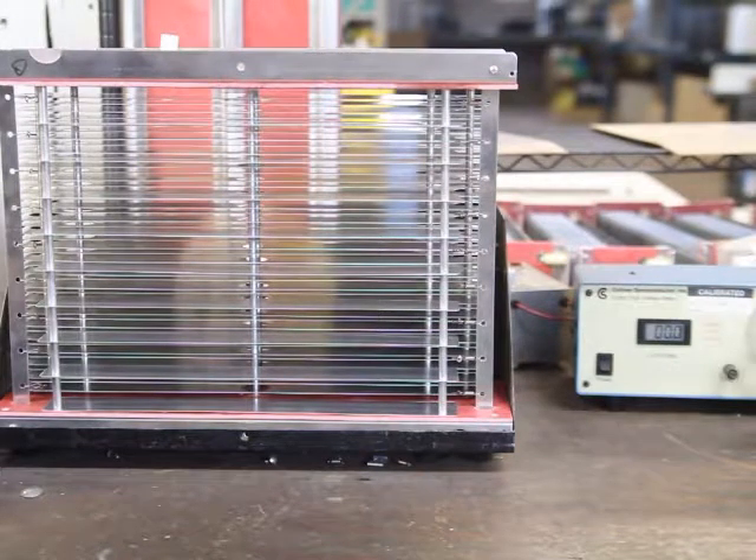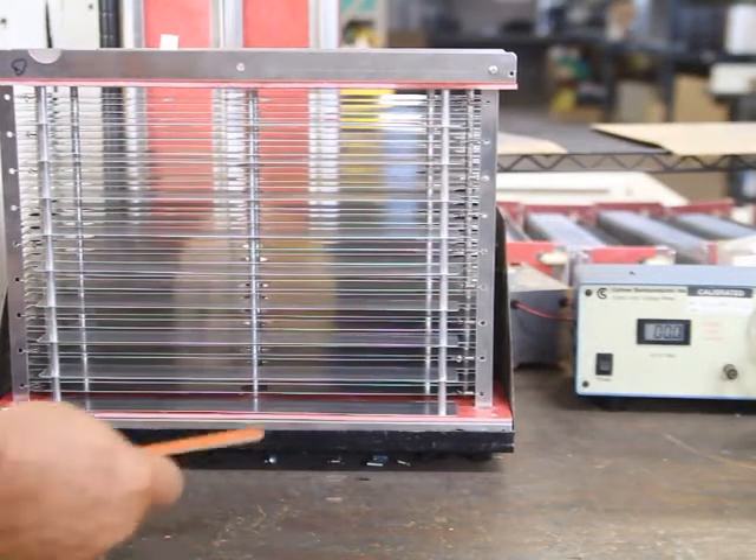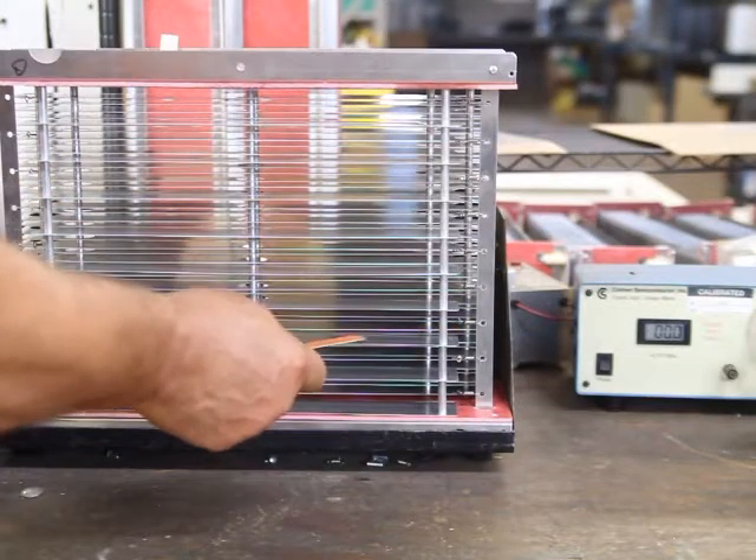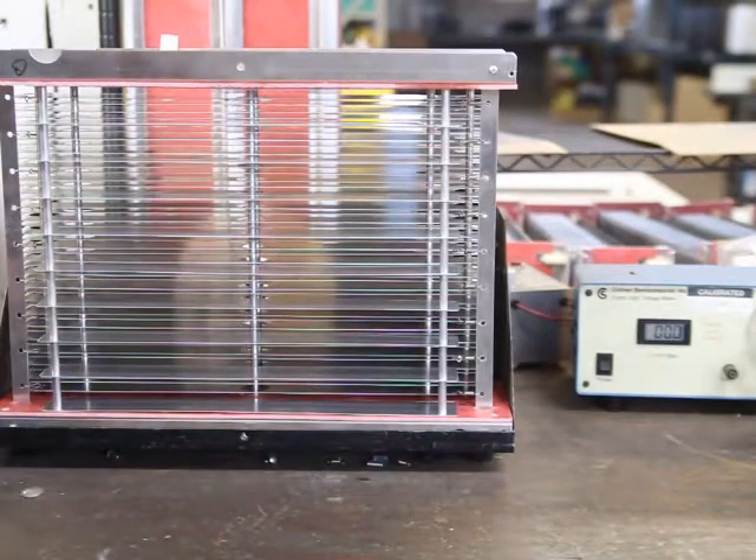Look and you're going to see that this is probably always happening in the same spot. After you can see where it's at, you have to identify where it's happening. In this case it's happening about ten plates up and about three to four inches over.